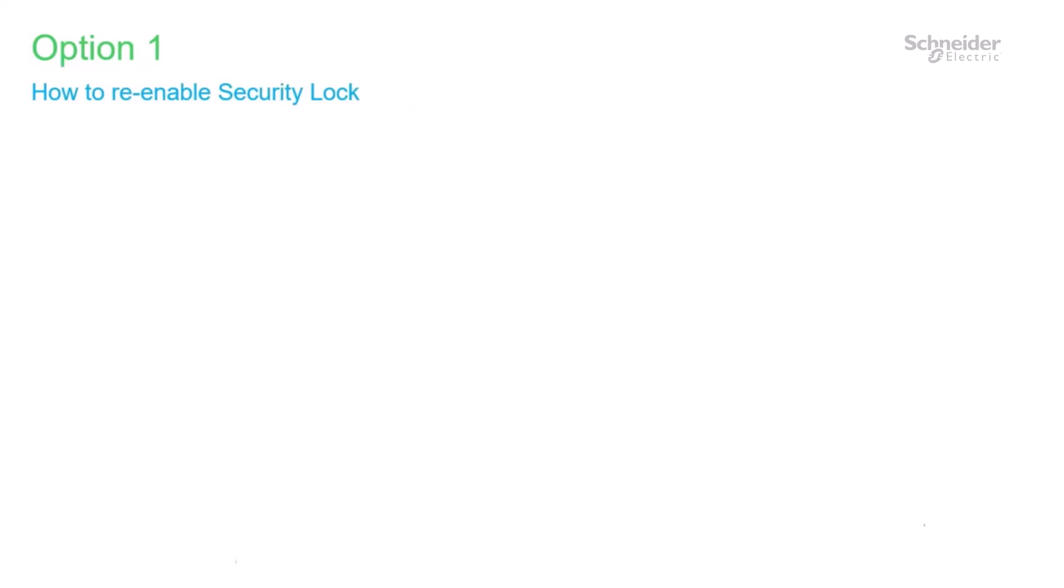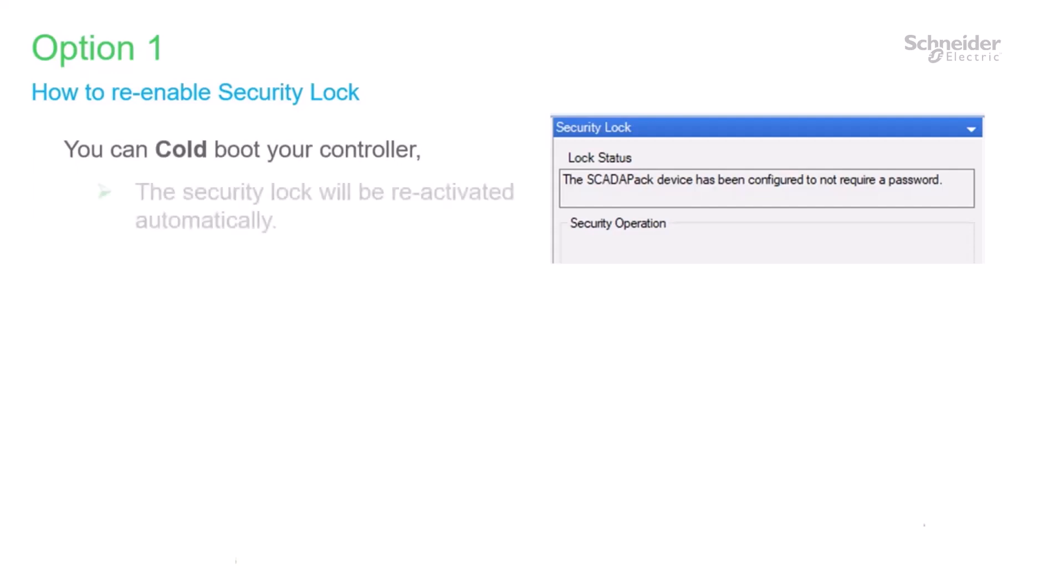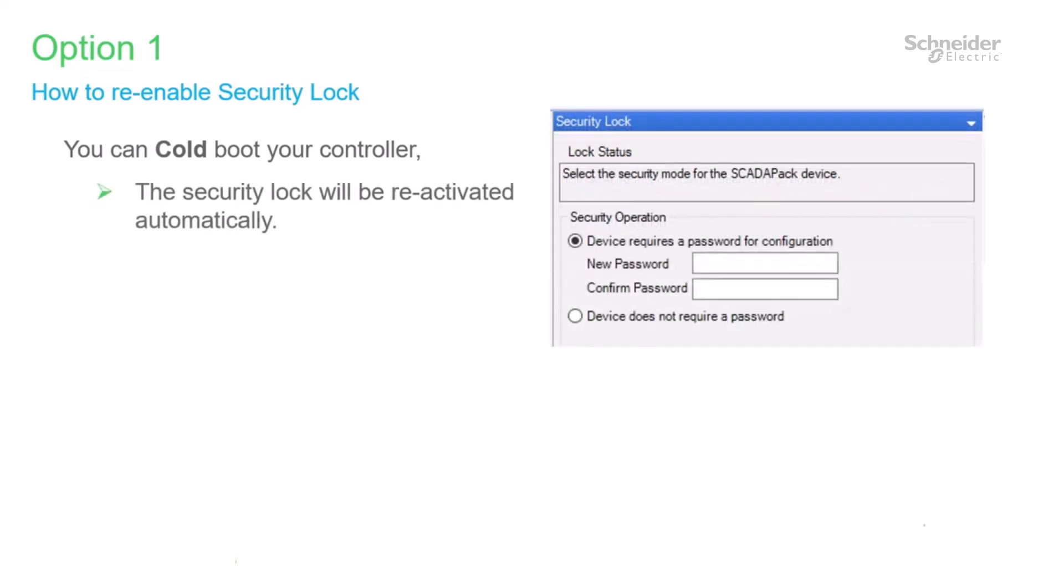Let's take a moment to look at how you would re-enable security lock. If you selected the controller security dialog, it would remind you that currently you do not require a password. Now recall we said that a cold boot or a service boot would re-initialize security locking. So if you do cold boot your controller and then go to the security lock dialog, it will have reactivated locking automatically, and the dialog will now look like this, which is what we saw earlier, and we can select a password or disable it again. However, a cold boot does erase your controller data. So that's a bit severe if you just want to re-enable control locking.